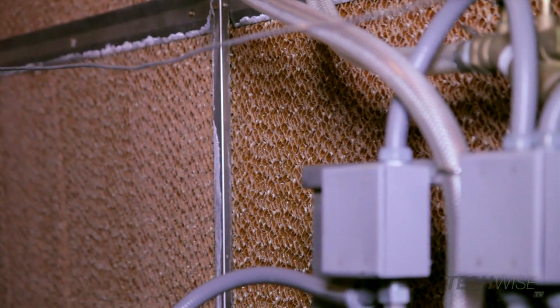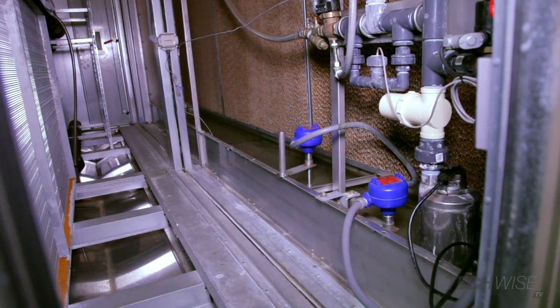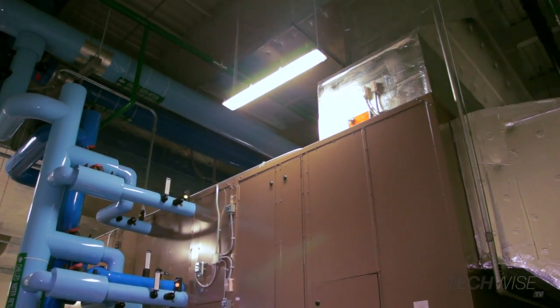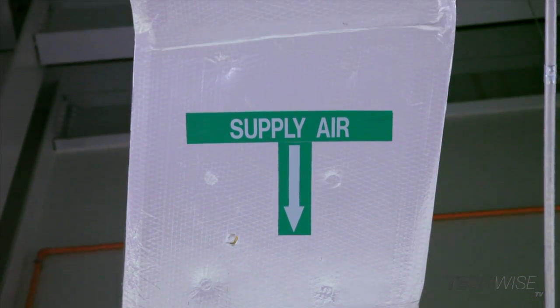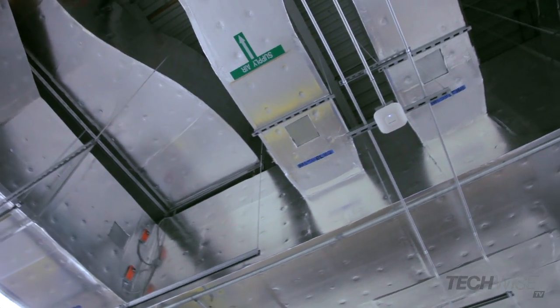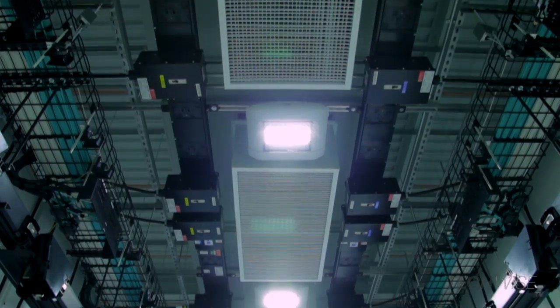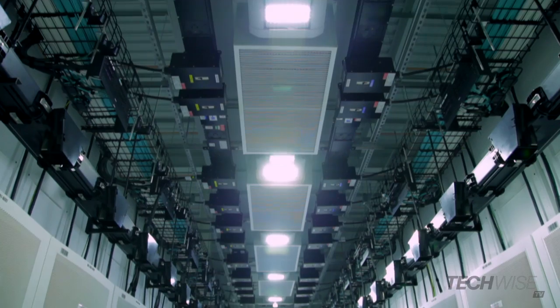The handlers themselves have multiple layers of filters with a fan at the far end that draws the air through, cleaning it. The air is then pushed up into this overhead plenum space that's above the data hall, and then that cool air naturally falls into the cold aisles.